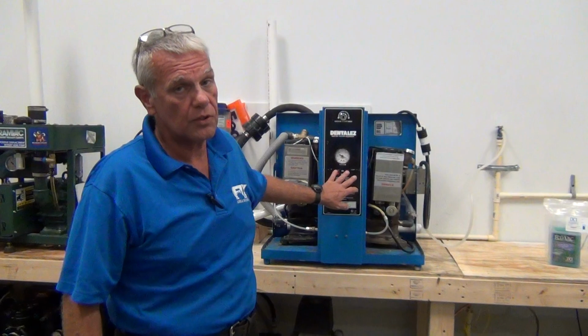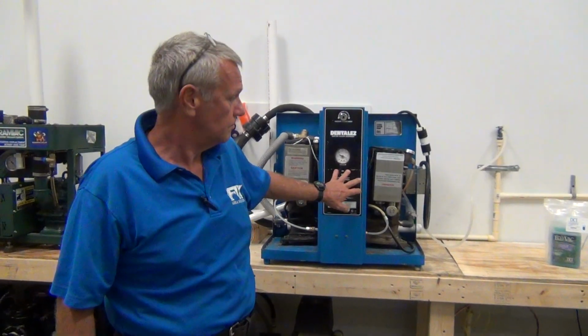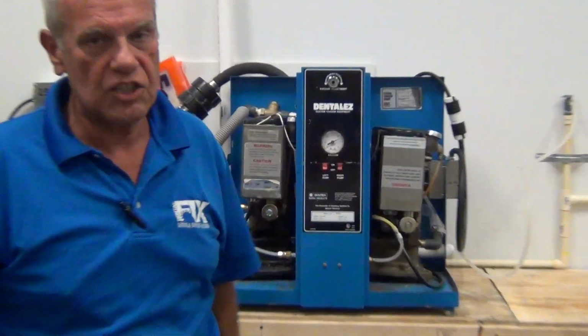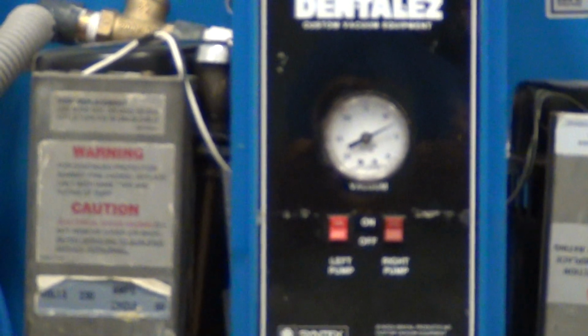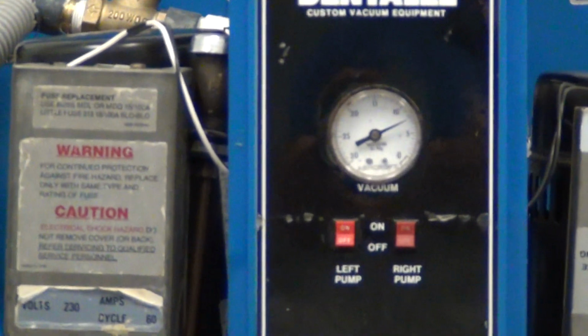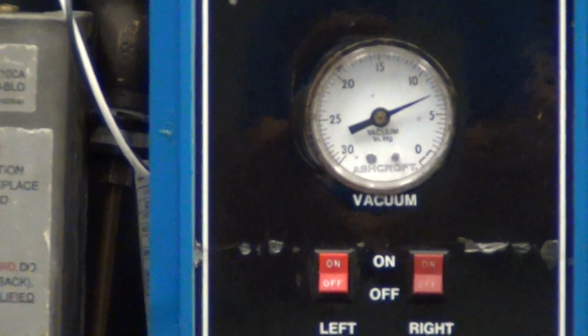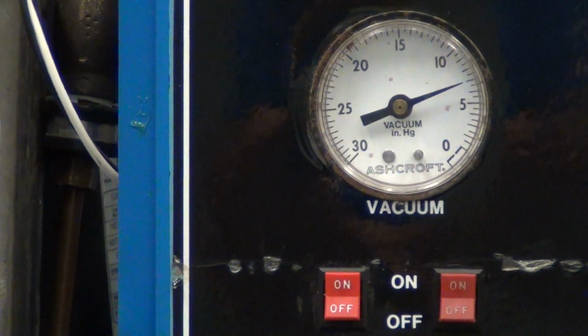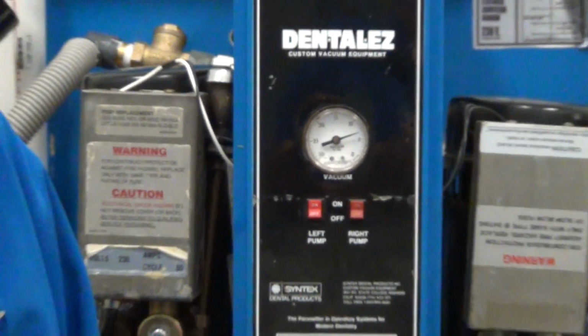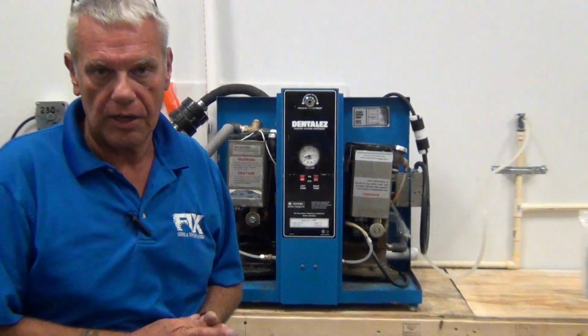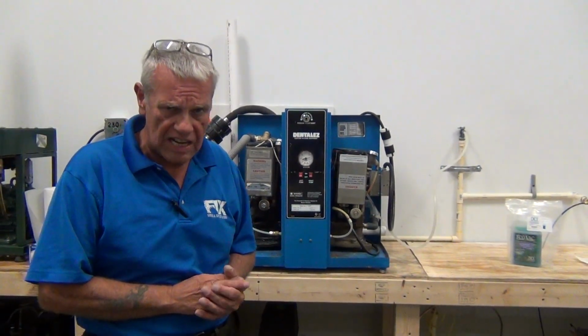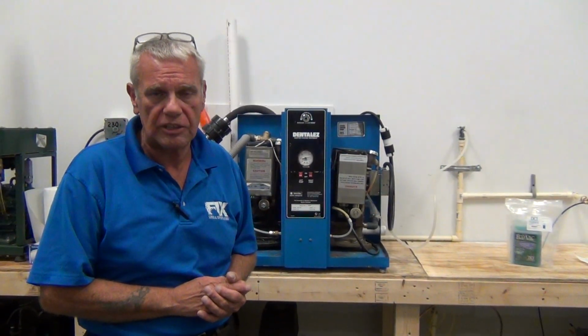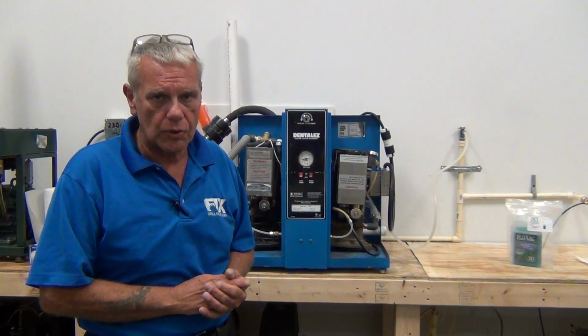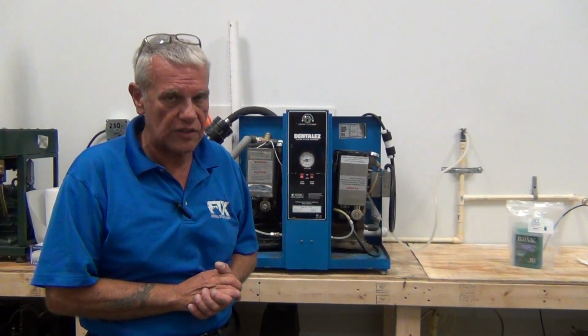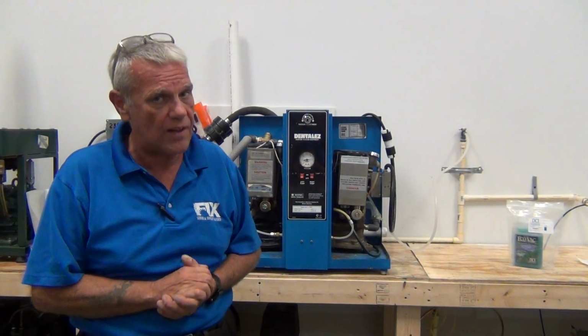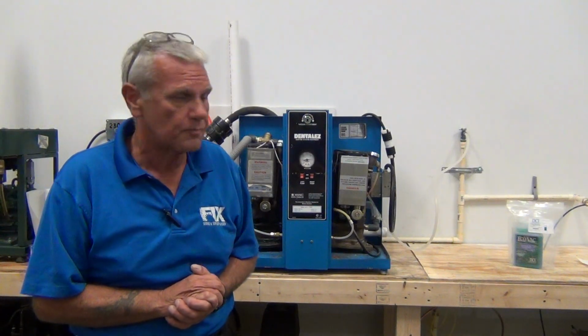To do so, we've got to turn on the pump. When you check the inches of mercury, run both pumps simultaneously. A lot of offices believe in running one pump and alternating pumps on weeks. That's not the way the vacuum pump was designed to operate. The vacuum pump was designed to operate both pumps simultaneously. The doctor's really doing himself a serious disservice if he does not operate both vacuum pumps simultaneously.